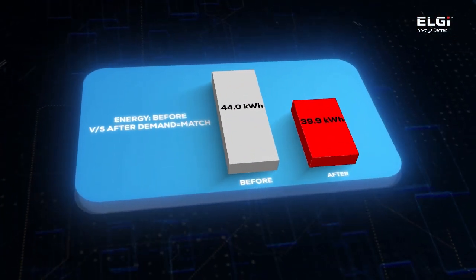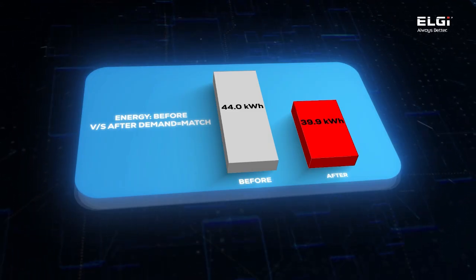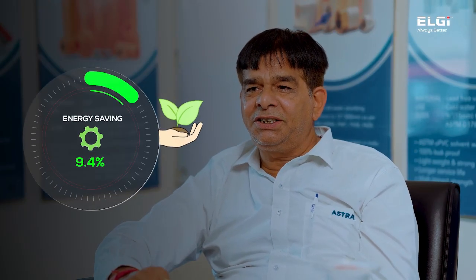To understand the benefits of the demand-match system, we installed an EG37 compressor with ELGi's demand-match system alongside our existing compressor and compared their performance over a defined period. The results were impressive. With the demand-match system, our average energy consumption dropped from 44 kWh to 39.9 kWh per hour — a 9.4% energy saving. This translates to approximately 759 units saved over 9 days of actual running.